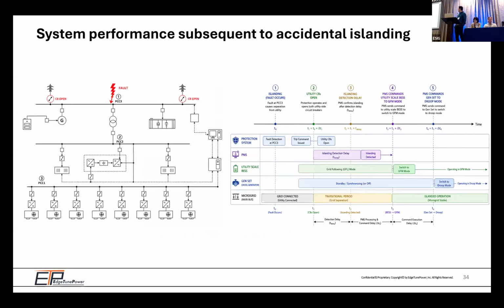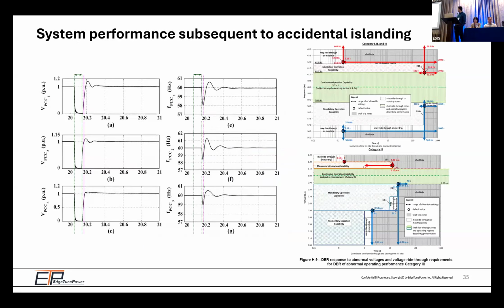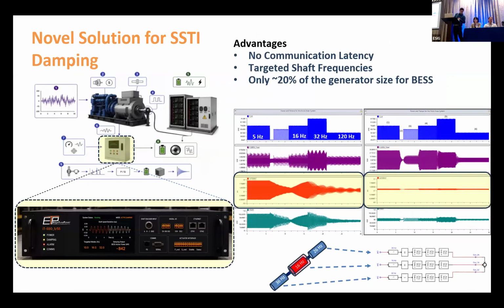Okay, so I'm going to probably bypass this one. We also did some accidental, unintentional islanding of the facility, which was a very important test for the data center project. And we showed compliance with IEEE 1547. IEEE 2800 is the norm in North America, but IEEE 1547 and 2800 are talking about voltage and frequency. It's just at the transmission and distribution level. Last one, great, I have 3 seconds.